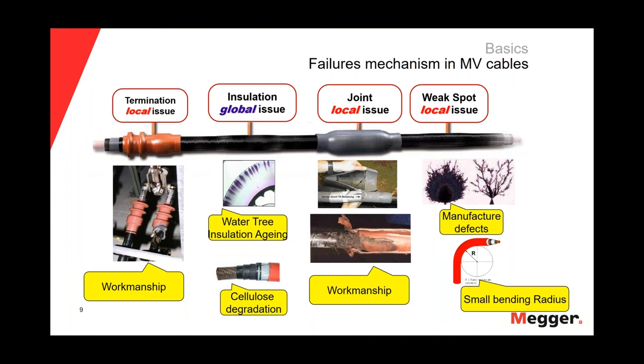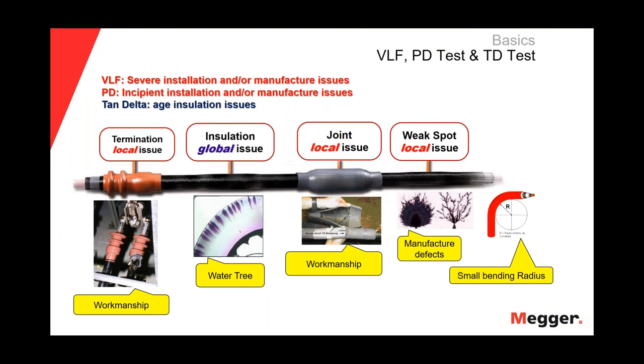In paper-insulated cables, when we have ingress of moisture or water, the water and the cellulose — the water and the paper — are not good partners, so that will start cellulose degradation. Depending on what problem we are dealing with, we can use different methods. If we are looking for severe installation or manufacturing defects, we use the VLF test. For incipient workmanship issues, we use partial discharge. And if we are looking for aging conditions of the insulation, we use the tan delta.